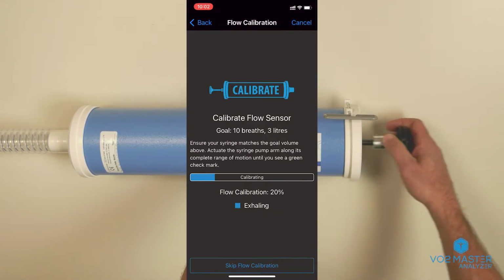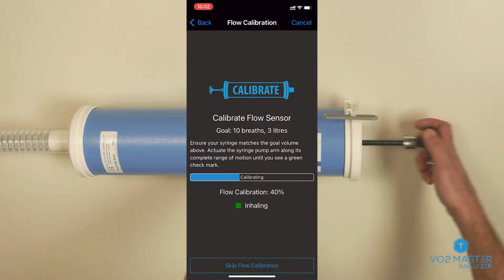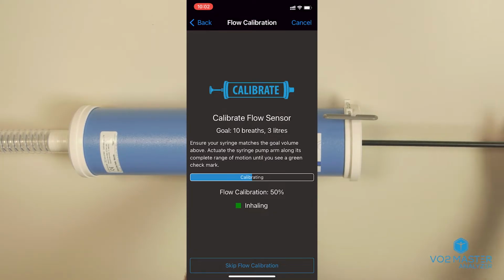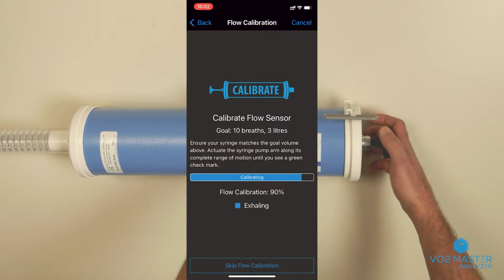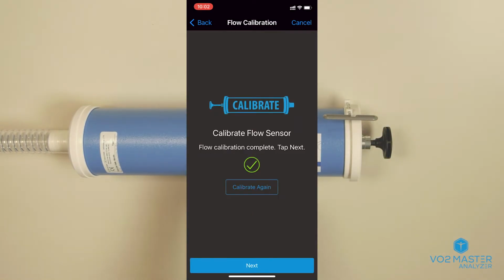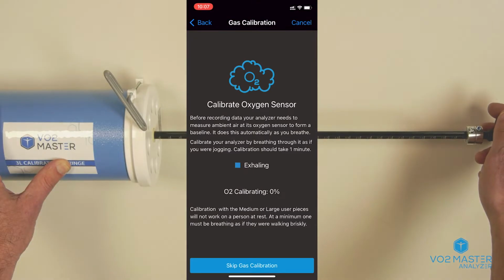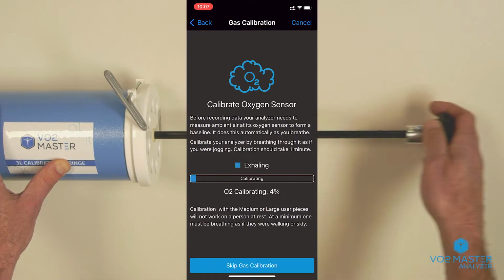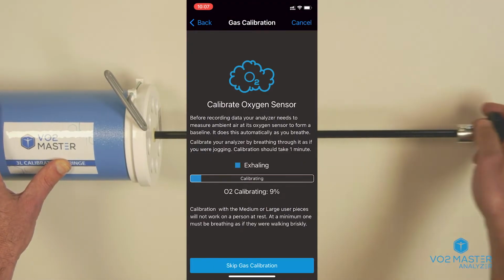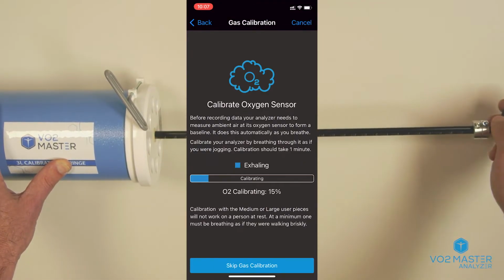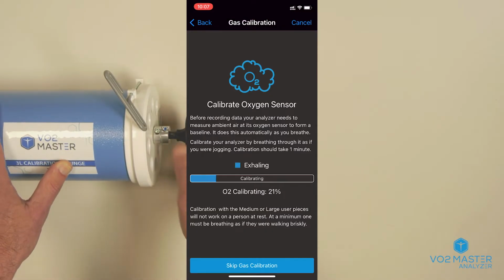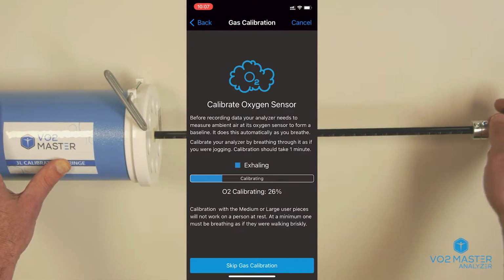Ensure the plunger does a complete cycle from start to finish on each stroke to guarantee 3 liters of air going through the analyzer. You'll hear a clunk at the start and the finish of the action. Do not bend the plunger arm while applying the breaths, and be careful not to hit either end aggressively, as this will limit the life of your syringe. Once flow is calibrated, you will move into O2 calibration. At this point, you can continue using the syringe or put the analyzer mask onto your client. We'll calibrate for oxygen here with the syringe.